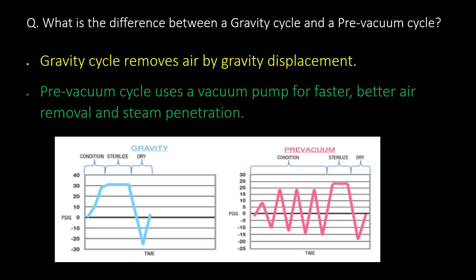What is the difference between a gravity cycle and a pre-vacuum cycle? A gravity cycle removes air by gravity displacement, while a pre-vacuum cycle uses a vacuum pump for faster and better air removal and steam penetration.